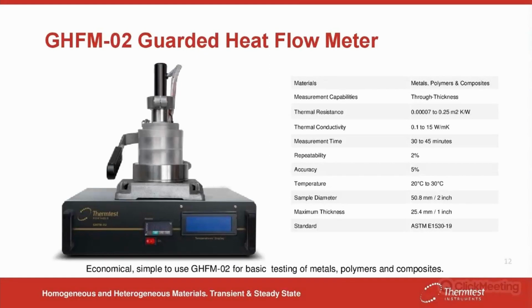And that allows us to have a chamber, rather two plates that come together in a guard furnace that limits the effects of lateral heat loss. So that's why we have that defined size. And again, the thickness can vary up to 1 inch.